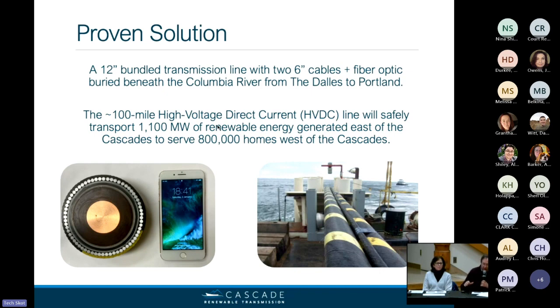What you see in the lower left-hand picture is a cross-section of the cable itself. You've got the large copper center conductor, and the voltage on it will be about plus or minus 320,000 volts, constant 24/7, 365, for as long as 40 years. That's not an unusual length of time for a project like this and the cables that support it. This brownish area is the insulation, which allows the copper conductor to be at such a high voltage.